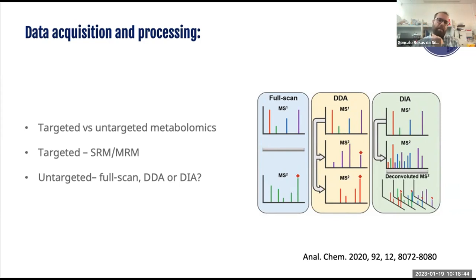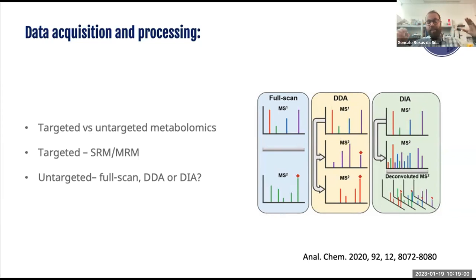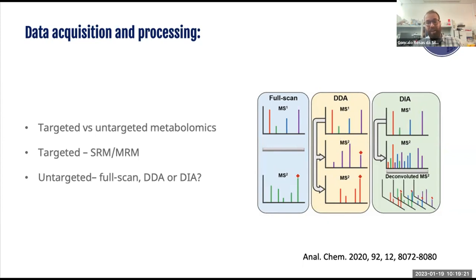DIA is basically where a lot of the technology is heading. It's an approach where the instrument, within a certain time window and mass range, tries to collect and fragment every single precursor ion, giving you a very thorough look at everything in your sample. It's the most powerful technique, but it also means the data can be incredibly complicated to extract useful information from. Justin will give you a nice rundown of the computational approaches available here.